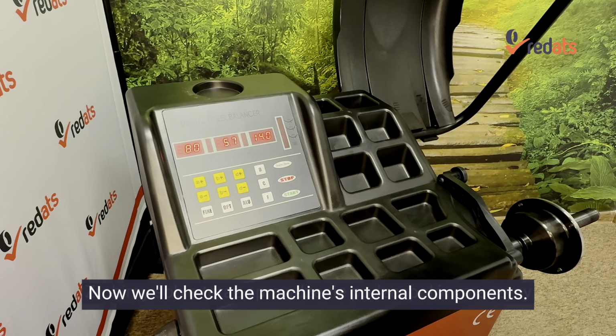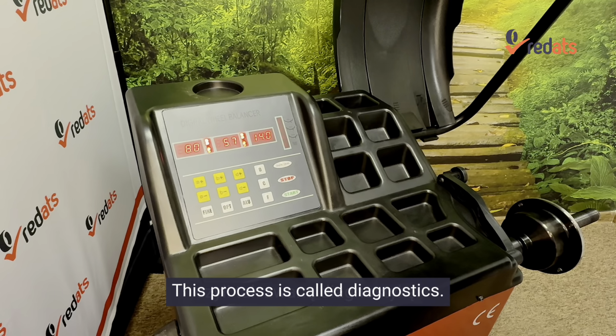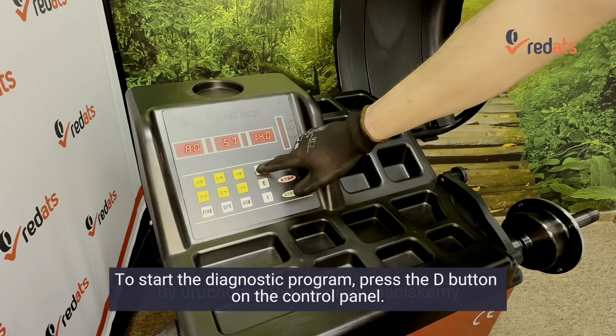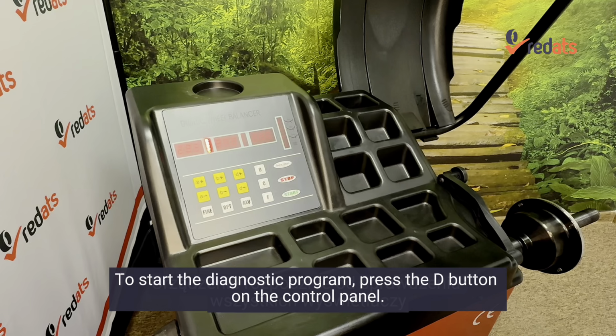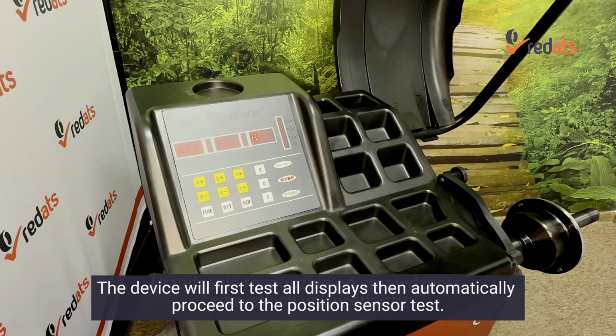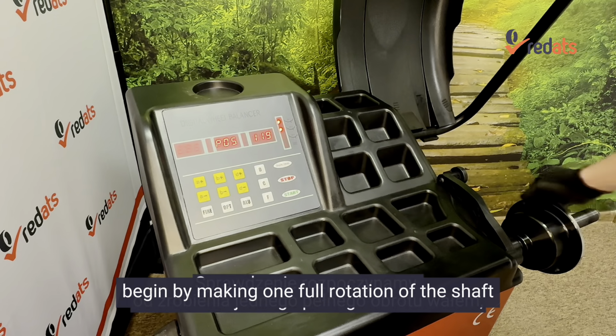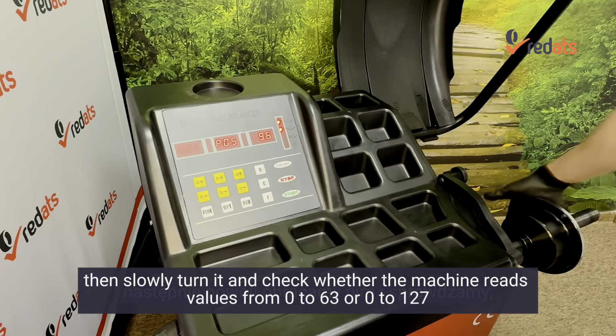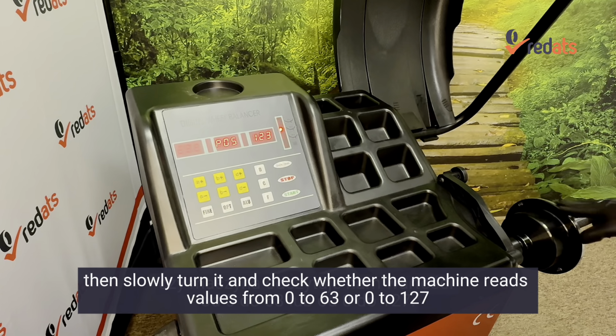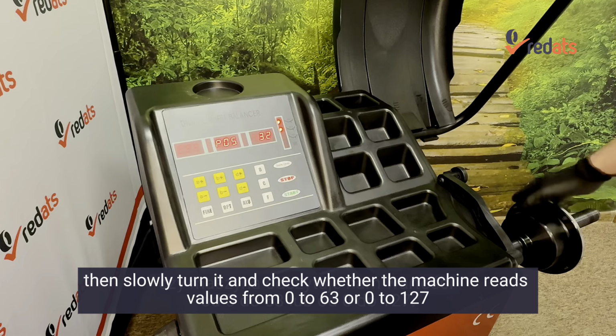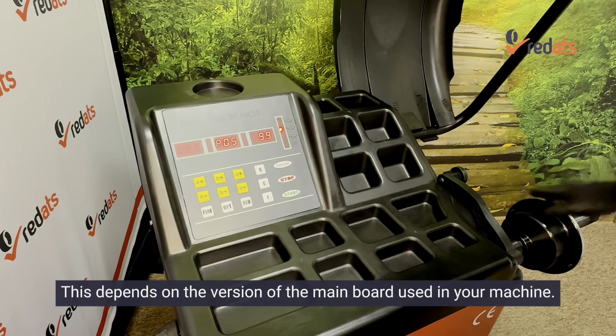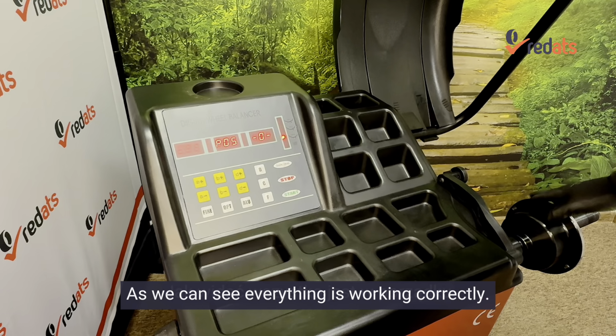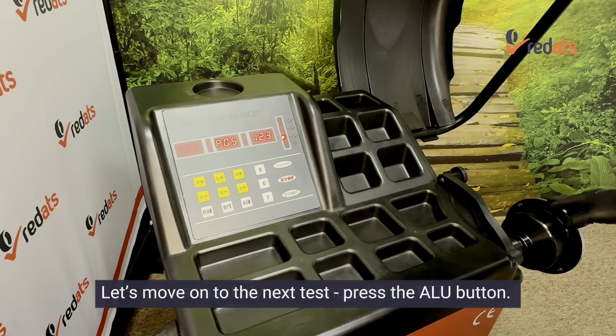Now we'll check the machine's internal components. This process is called Diagnostics. To start the diagnostic program, press the D button on the control panel. The device will first test all displays, then automatically proceed to the position sensor test. Begin by making one full rotation of the shaft, then slowly turn it and check whether the machine reads values from 0 to 63 or 0 to 127. This depends on the version of the mainboard used in your machine. As we can see, everything is working correctly. Let's move on to the next test.